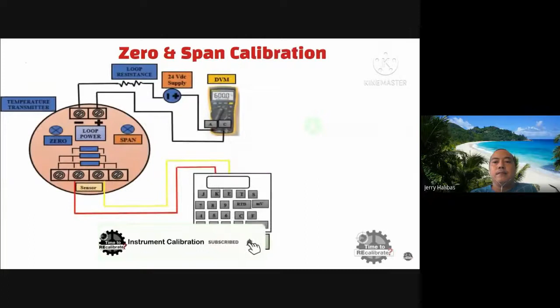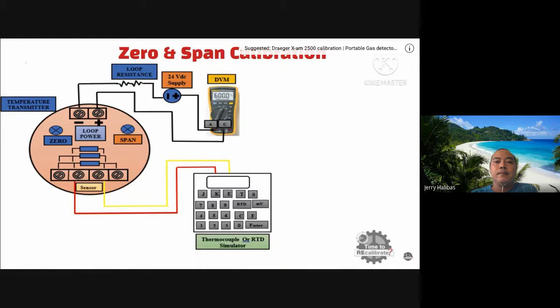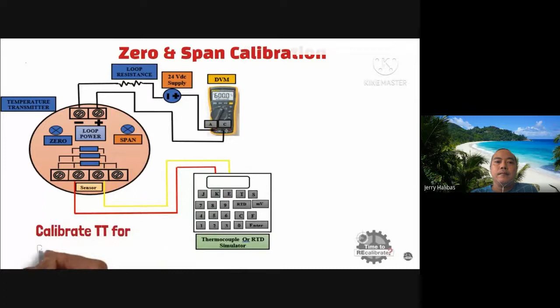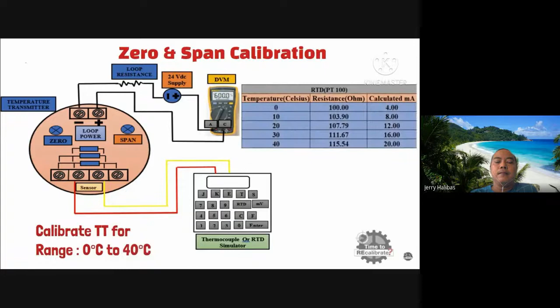In this section, I am going to show how to perform zero and span calibration of temperature transmitter. First of all, in order to perform calibration of temperature transmitter, we need calibration range. For example, let's assume that this temperature transmitter need to be calibrated for range 0 Celsius to 40 Celsius. Also, let's assume that RTD-PT100 will be used as sensor after calibration. So, this is a reason that RTD-PT100 resistance table is being used for this calibration. As you can see from the table that RTD-PT100 has some specific or standard resistance values at some specific temperature. You can also find this table in manufacturer datasheet of RTD-PT100. We will use these resistance values to calibrate temperature transmitter.